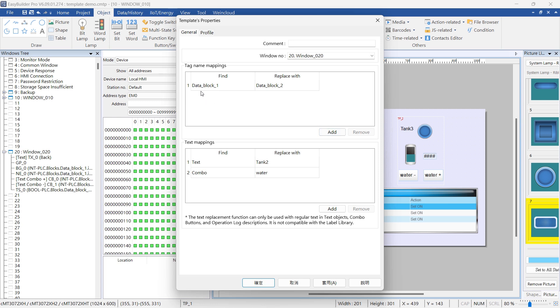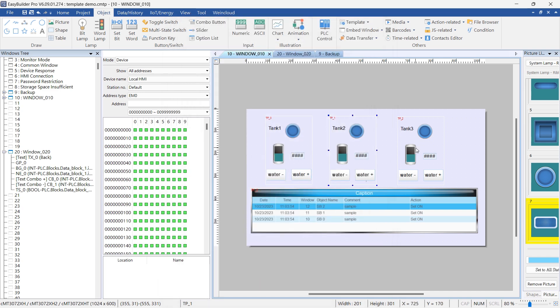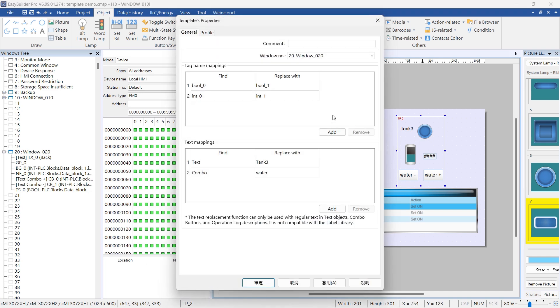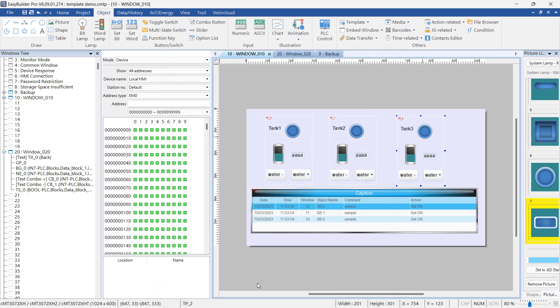For the second template object, add a new tag mapping rule replacing data_block_one with data_block_two in the tag names, and set Tank 2 as the text mapping rule. For the third template object, modify the tag mapping rule to replace bool_zero with bool_one and int_zero with int_one in the tag names, and set Tank 3 as the text mapping rule.